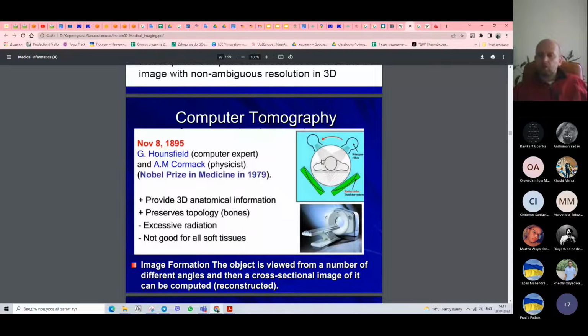We can find sources which step by step change location, and symmetrically to this location change, the sensor which identifies the value of X-ray which comes through the body rotates synchronously. This gives a chance to completely understand what kind of tissue and what location are present in the patient for any cross section.